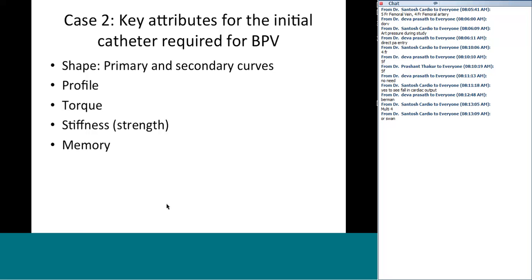Memory: after a couple of uses, the catheter should continue to do what it is doing. It shouldn't become completely useless, which happens sometimes, especially with reused catheters. The tip should be atraumatic - while you're working inside the heart, the tip can actually damage it if it's not. So these are the essential attributes, and you need to analyze the catheter in that fashion.